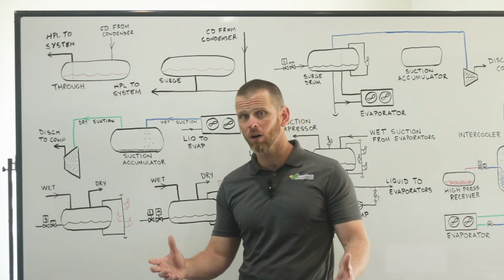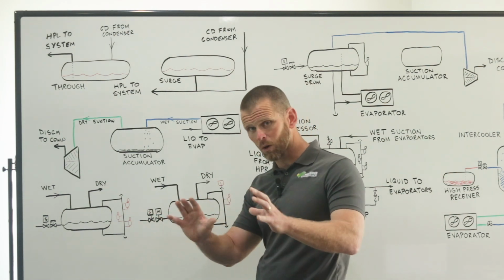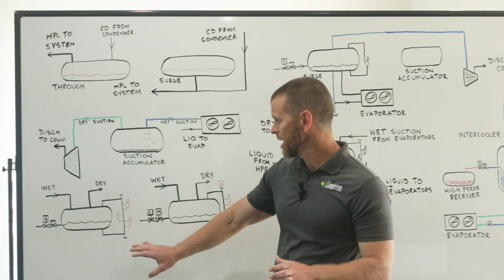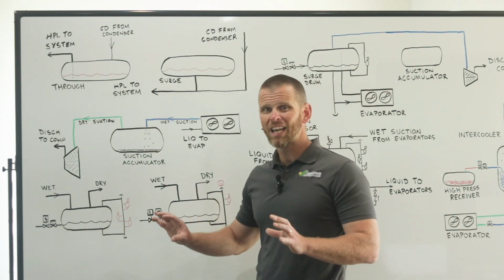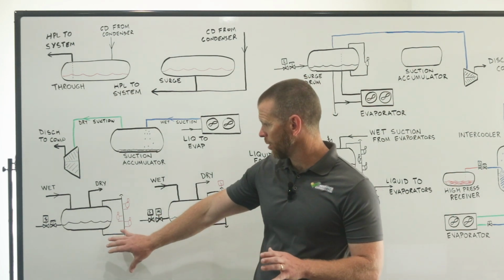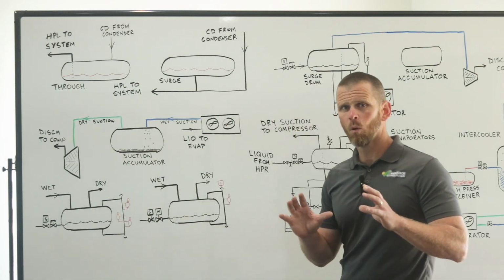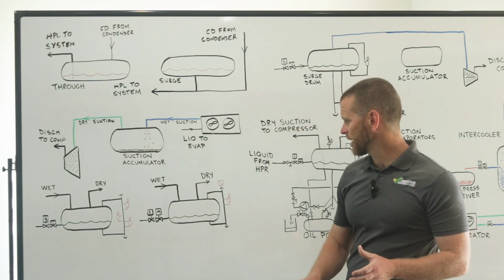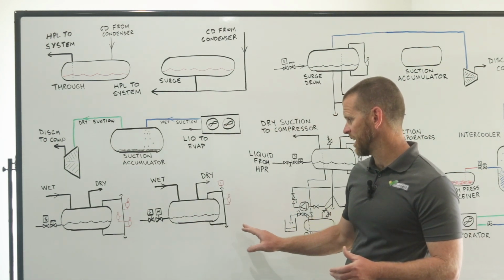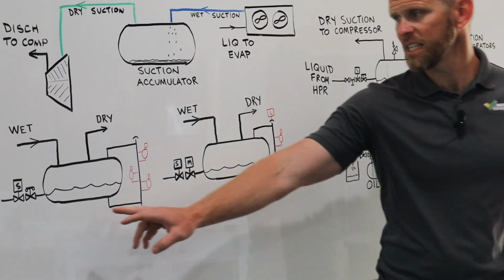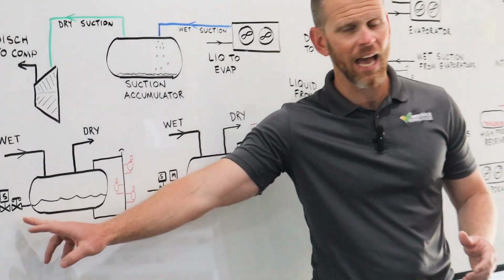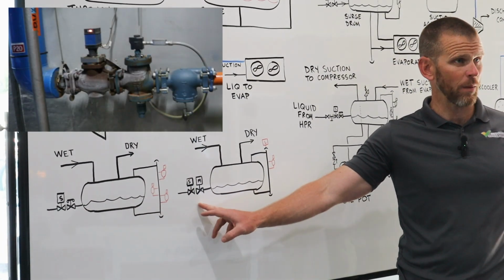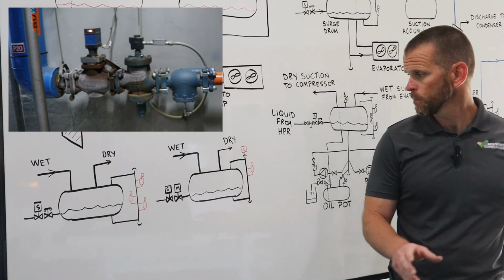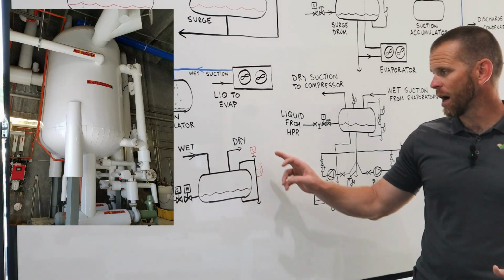You could have even more float switches, more cutouts. Let's say there was a liquid transfer system, but this is providing that example. Historically, this is widely how recirculators were set up. On a more modern recirculator, it's more common to see a setup similar to this now. Notice I've replaced the hand expansion valve that we had with a motorized expansion valve, so we're a bit more sophisticated. And instead of the float tree, we now have a level probe.